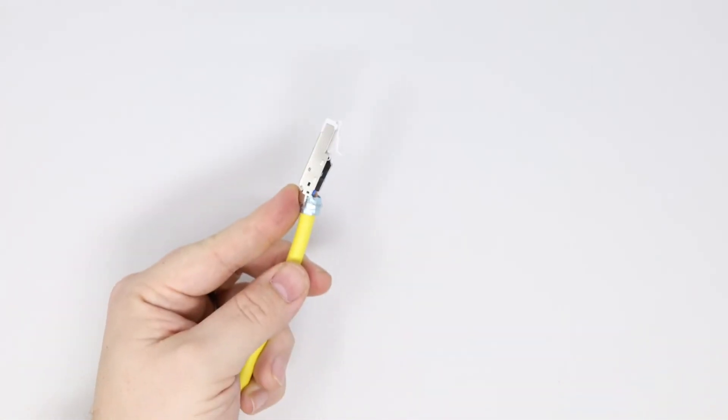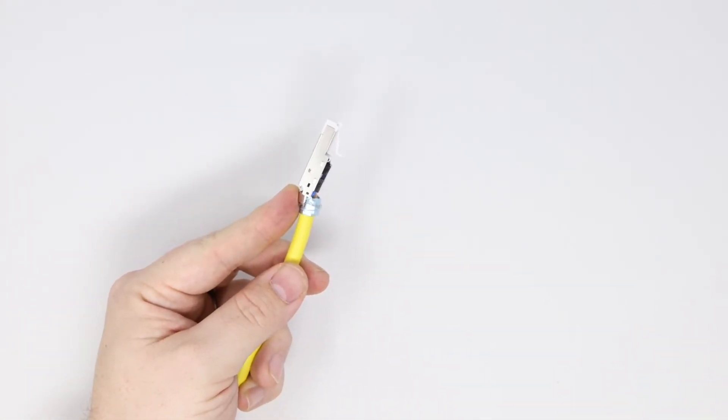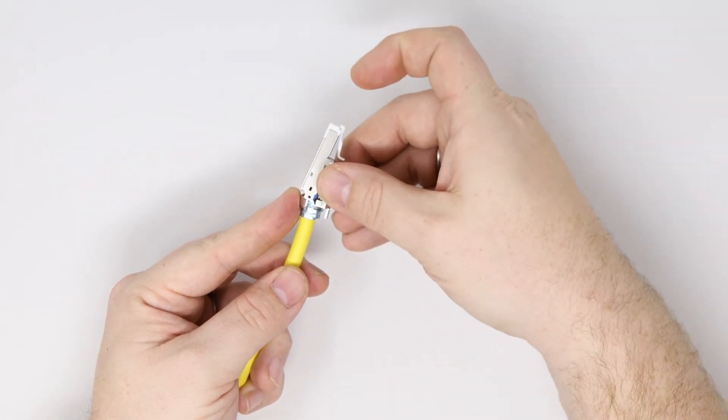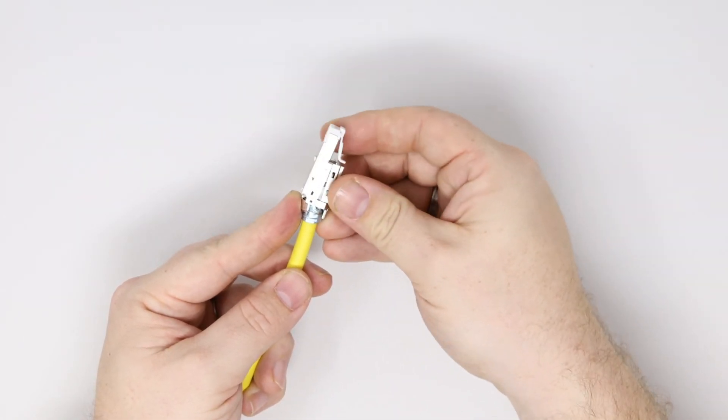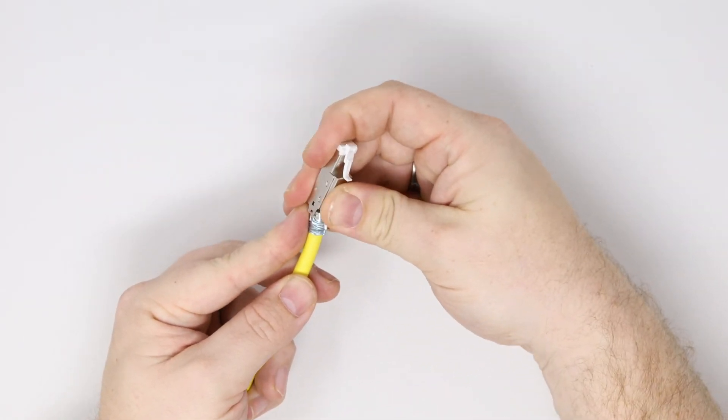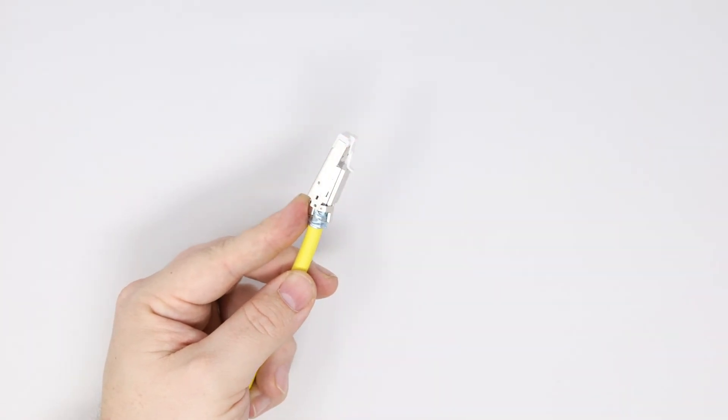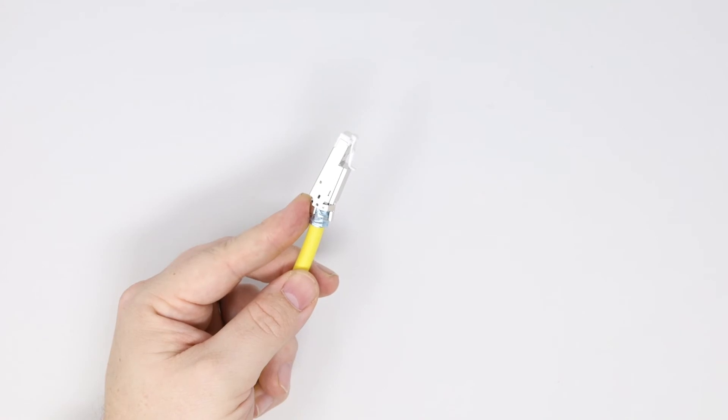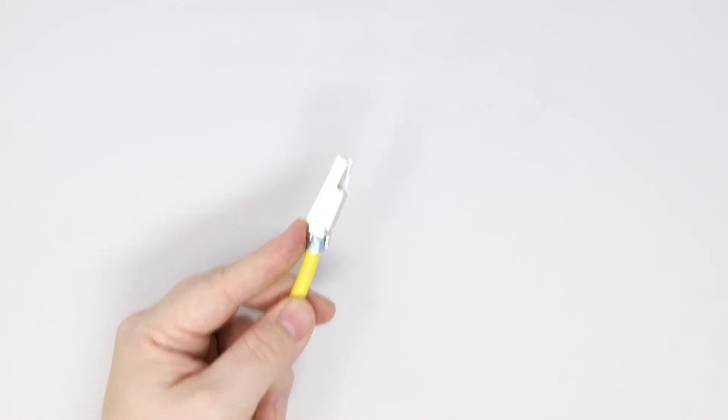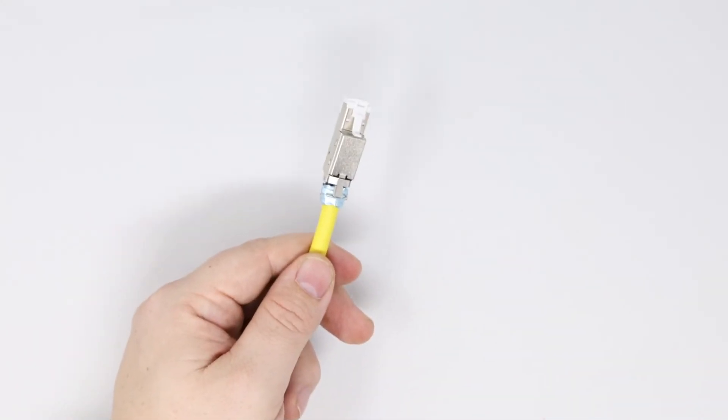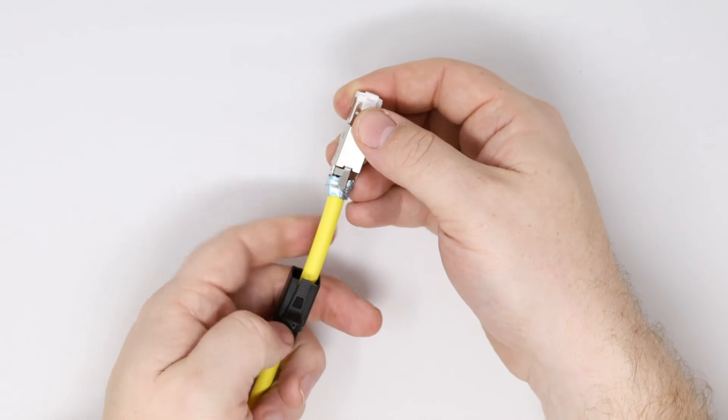Now place the connector cover onto the main connector housing. This is achieved by aligning the indentations on both connector parts. Use your thumb or parallel pliers again to ensure both halves of the connector are now securely in place. This will also ensure that the shielding of the cable sits correctly in the rear metal flanges of both the cover and the main housing of the connector, forming a 360 degree termination of the shield.